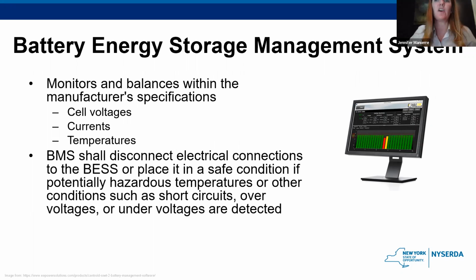Okay, I've talked about this a couple times, but it's really important to remember that it's there and what it does. The energy storage management system, the eyes, the ears, the brains, it monitors, not just monitors, but also balances the system within the manufacturer's specifications. It's looking at cell voltages, currents, temperatures. Like I said, if one cell starts to overheat, it can isolate that cell and sort of shut it down and prevent anything from escalating.